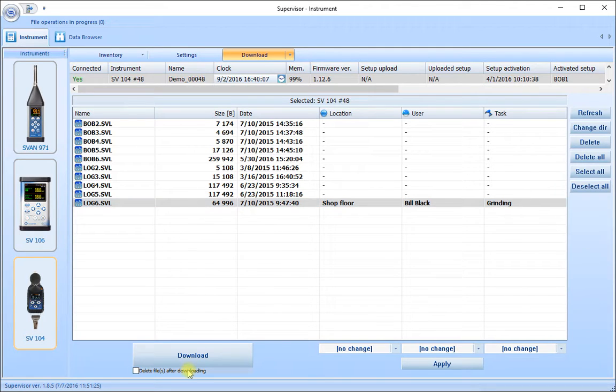Having highlighted the run now, we can just click on the download button and this information will be transferred from the instrument, copied from the instrument's memory to our database. It still stays in the instrument's memory until we delete it, so if necessary it can be downloaded to a different PC and a different person's database.